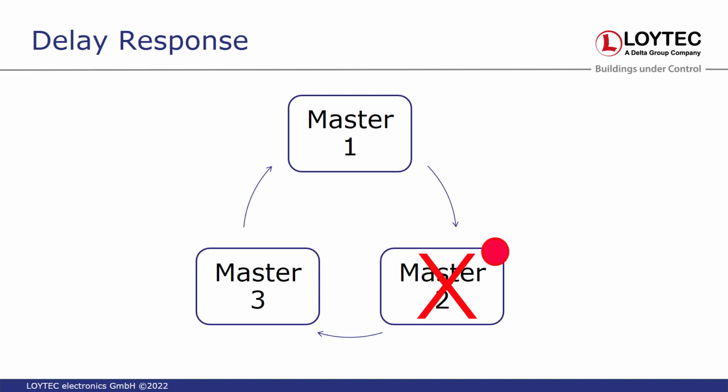If every node is responding fine, then one gives the token to the next, to the next, and this works fine. But if there are only a few nodes that are not passing on the token, then this slows down the whole network traffic. And I think this is the case. If you have these issues, you can check on the statistics pages, like Hans said, and you would see that the token is lost and that this is the issue.